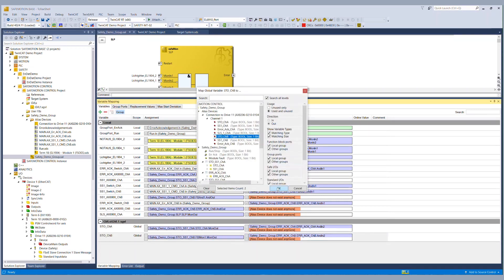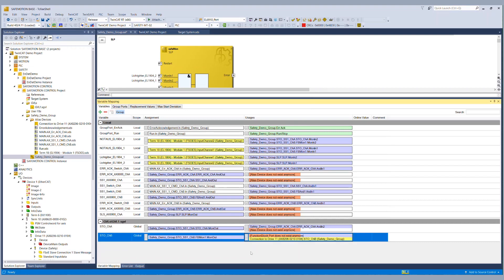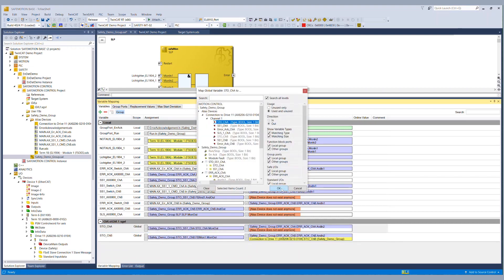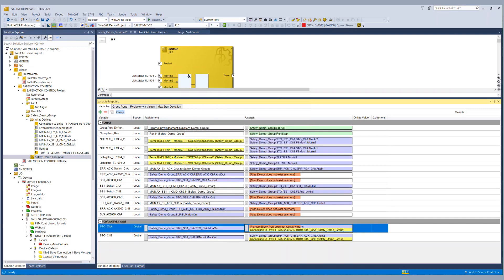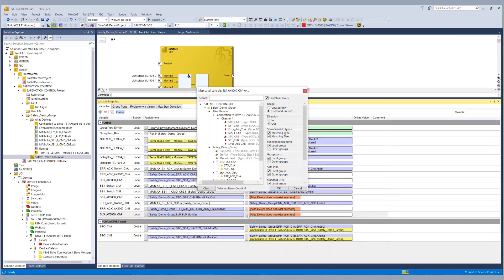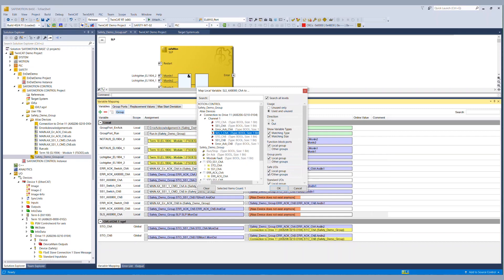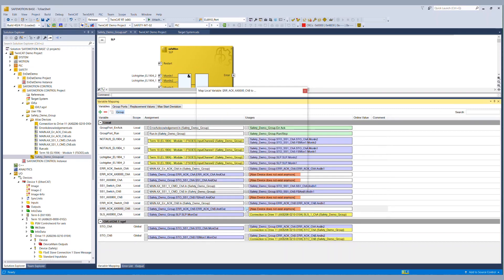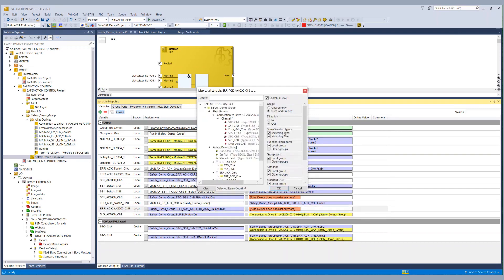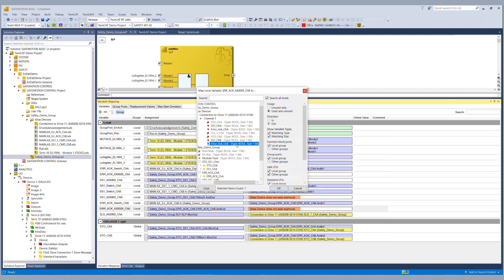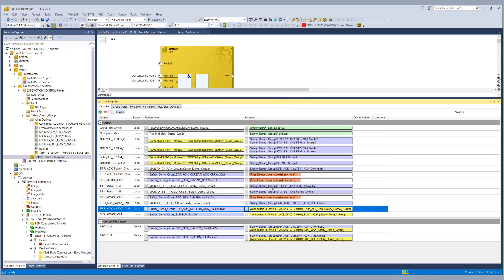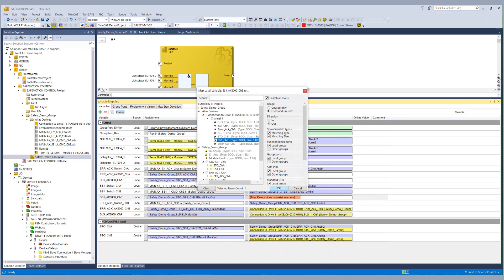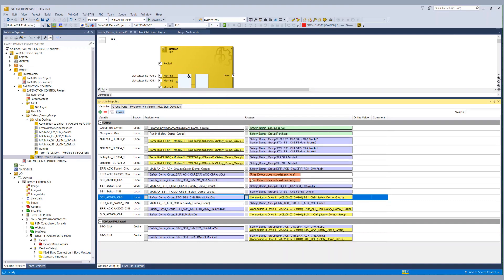Because we are using an already existing project so we connect the STO signals for channel B and channel A. We connect the SLS bit which we are using today for the tutorial and of course the missing ACK and SS1 signals for both channel B and channel A.